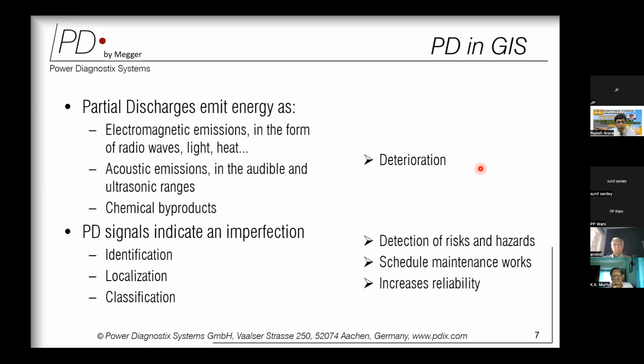Now, just measuring the partial discharge is not where we have to stop or what is going to help us. We also need to understand where inside the insulation this imperfection causing partial discharge is happening, and for what reason. Once we know these two things, where and why, we can have certain detection mechanisms or take some precautionary measures and schedule maintenance work so that we can increase reliability. So these are the reasons why we should measure partial discharge. Ultimately we can track down, do the maintenance and increase the reliability of the operating GIS.